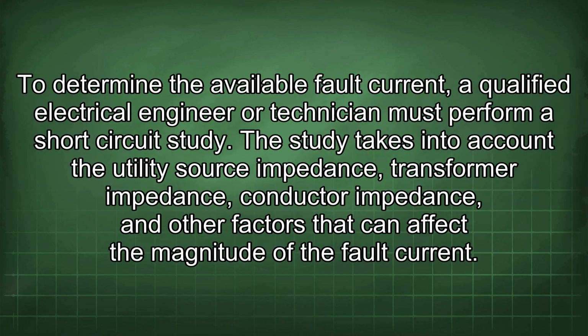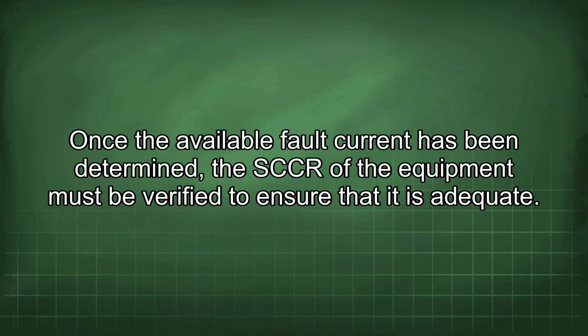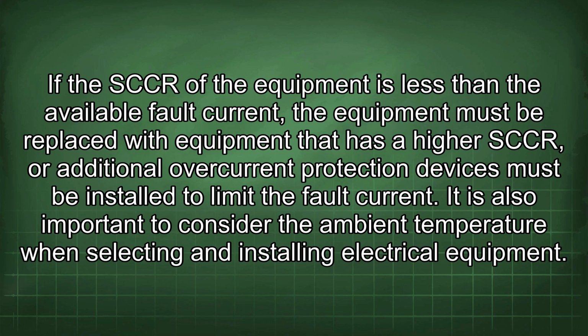To determine the available fault current, a qualified electrical engineer or technician must perform a short-circuit study. The study takes into account the utility source impedance, transformer impedance, conductor impedance, and other factors that can affect the magnitude of the fault current. Once the available fault current has been determined, the SCCR of the equipment must be verified to ensure that it is adequate. If the SCCR of the equipment is less than the available fault current, the equipment must be replaced with equipment that has a higher SCCR, or additional overcurrent protection devices must be installed to limit the fault current.